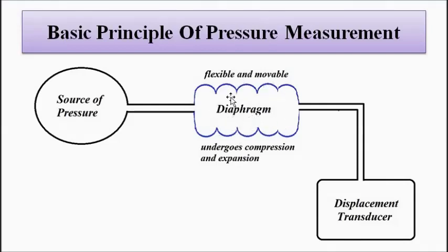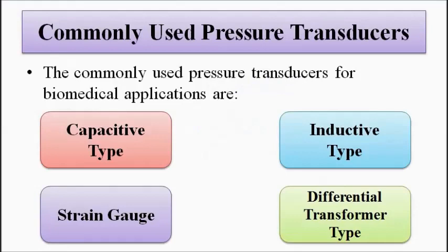So the displacement is dependent on the compression and expansion of the diaphragm, and the compression and expansion of diaphragm is dependent on the fluctuation of pressure. So the displacement is indirectly related to pressure fluctuations.